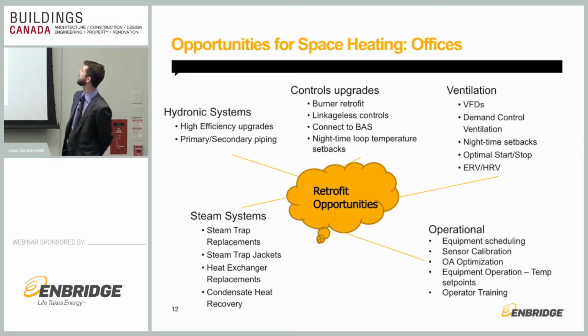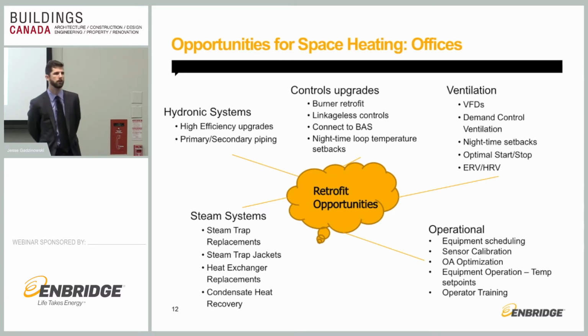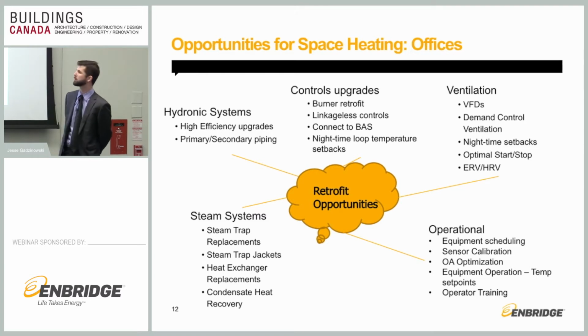For ventilation, we're looking at VFDs, demand control ventilation, nighttime setbacks again, optimal start-stop programs. So once you connect to the BAS and you try and tighten that on-off time between, try to shave an hour in the morning or maybe shave an hour in the evening. There's a substantial savings there as well, especially if you're doing it over multiple rooftop units or multiple systems.